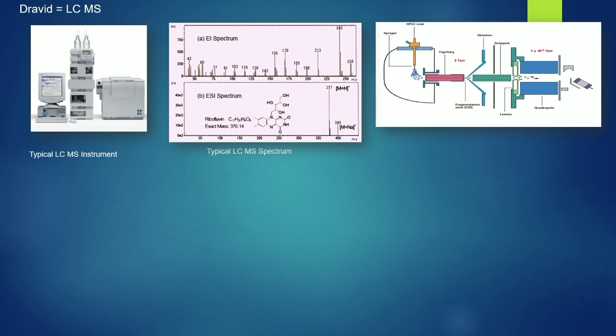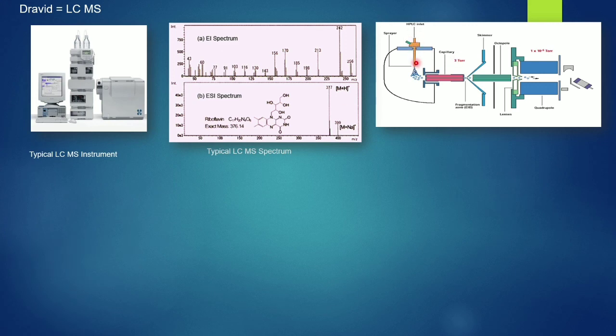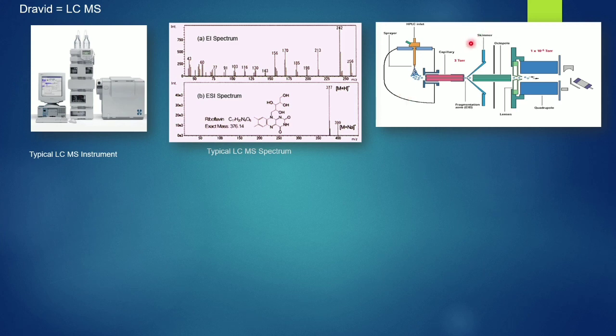What exactly is happening in an ESI LCMS instrument? From the column, the column will separate your analyte and it will come to a capillary tube — you can see this orange color, that is the capillary tube. In this capillary tube we are keeping a temperature of 100 to 120 degrees Celsius, which is just slightly above the boiling point of water. The analytes come from the column with the HPLC mobile phase containing water, acetonitrile, or methanol. At that temperature your solvents will evaporate. If you keep a droplet of water on a table it remains as a liquid droplet because of surface tension — any liquid with surface tension will remain in the form of a droplet.